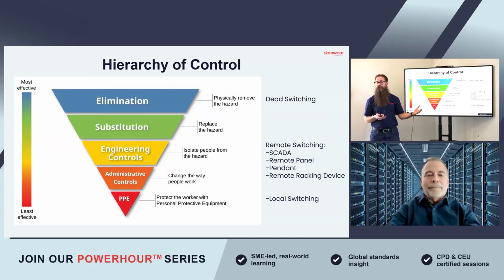We could ask the utility or the DNO to turn off the entire site from remote, just open the breaker from the control room, and then we've got a dead site. It probably isn't reasonably practicable to turn everything off, and it probably introduces wider risks such as no light and no small power, which would cause us a bit of a nightmare. So typically we can't eliminate the risk in its entirety. There may be some substitution processes in place, but from a switching perspective it often falls into engineering controls. So we look at things like remote switching options that we've already discussed.